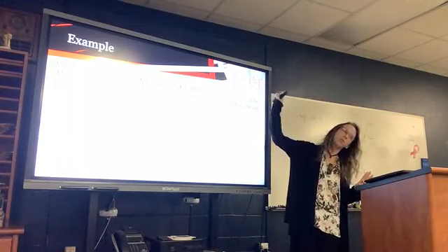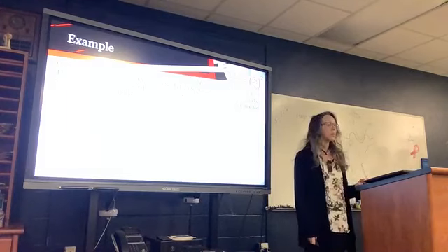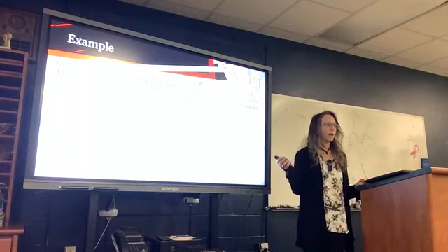So don't forget, write it first. Now you could plug in just mAs, just time, or mAs, and distance. Did you identify your D1, mAs 1? And we're looking for mAs 2, right? Did we remember to square? Don't trust your brain. Go ahead and put it in the calculator, even if it's 2 plus 2.